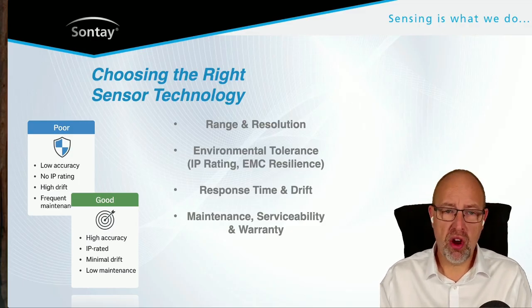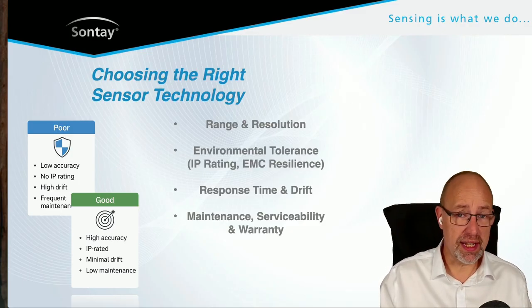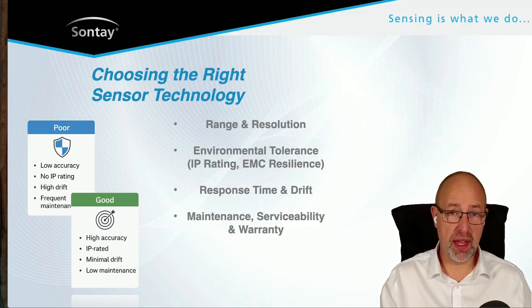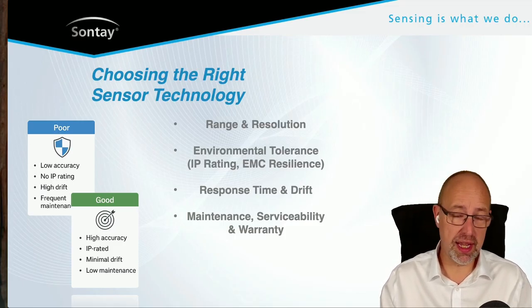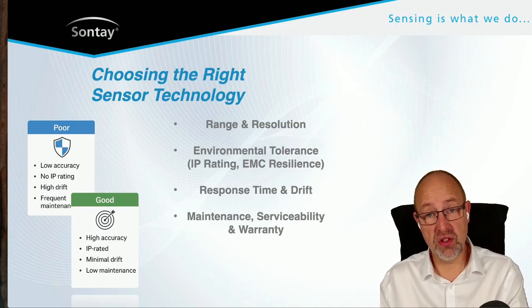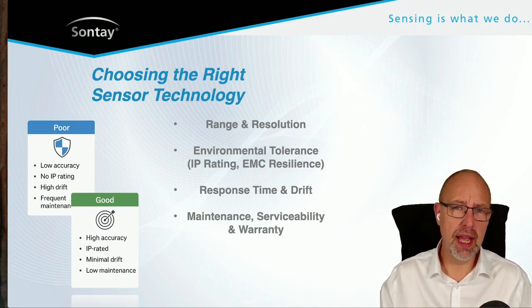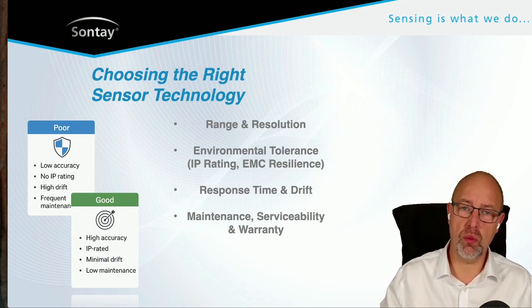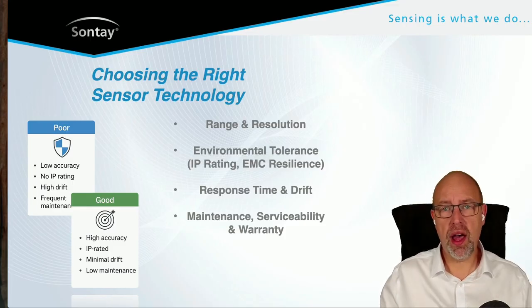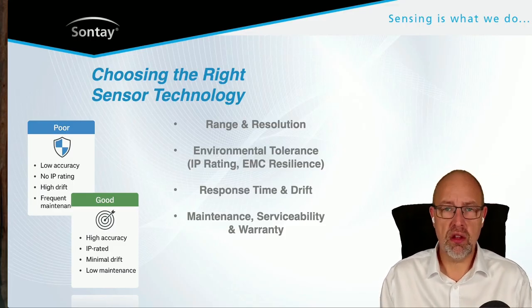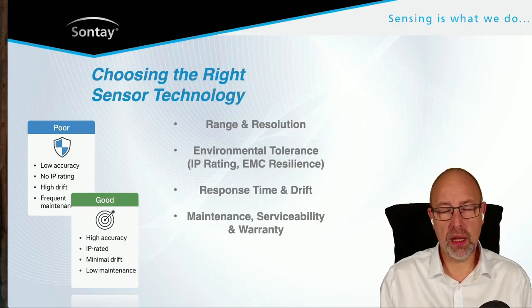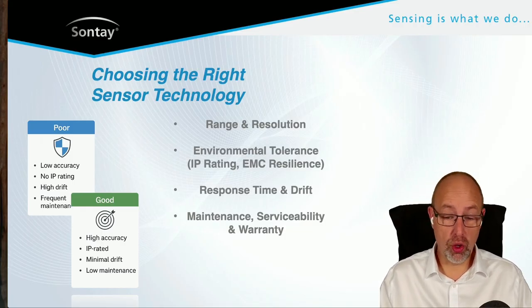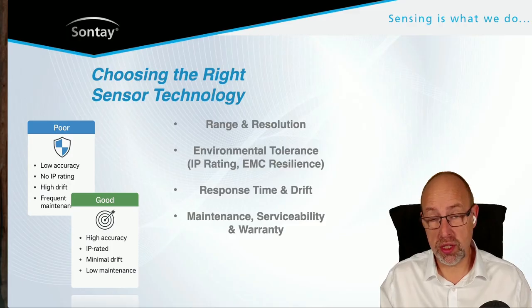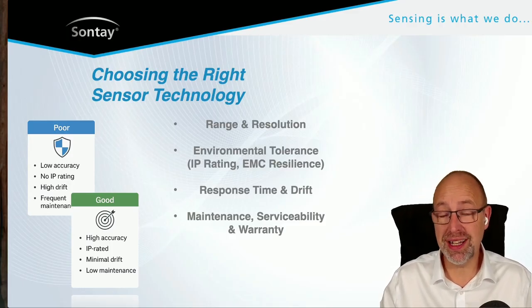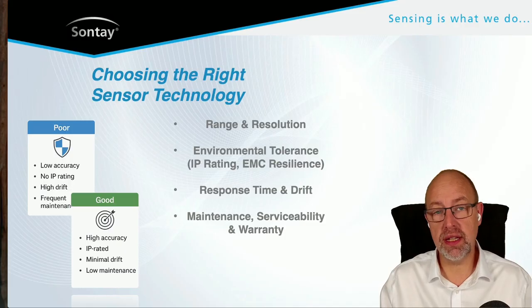You also need to think about environmental tolerance. IP ratings, ingress protection: when you're putting something in an environment where there is potential for ingress of dust, so solids and liquids, you need to think about that IP rating. Typically, we associate that with components which are going on a roof and are therefore going to be subject to the weather. But we also need to think about other aspects as well. EMC resilience, so electromagnetic compatibility. Data centers have got lots and lots of fast switching circuits in them, and so EMC resilience is something that needs to be considered in these spaces.